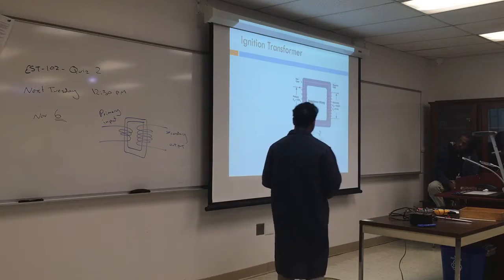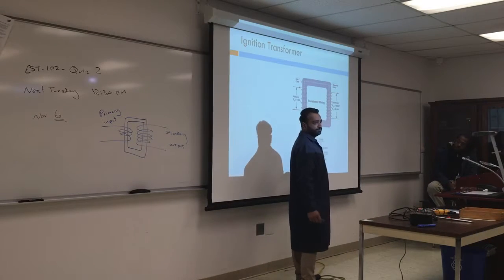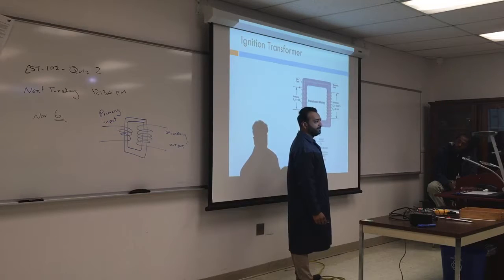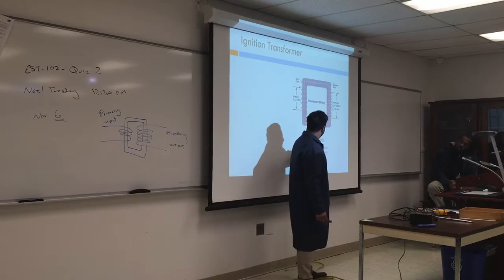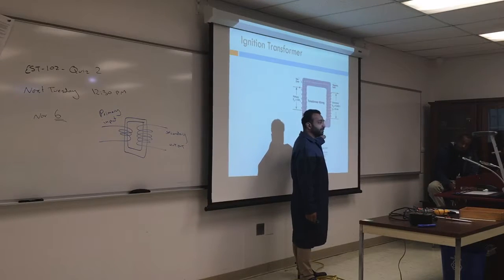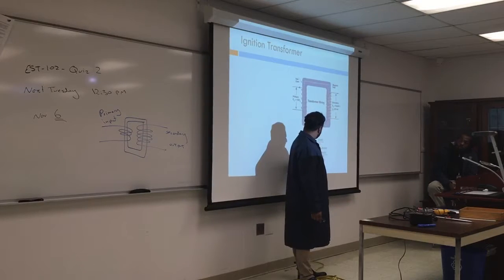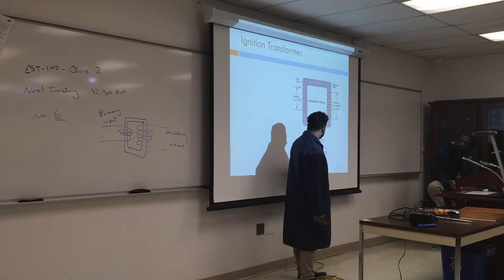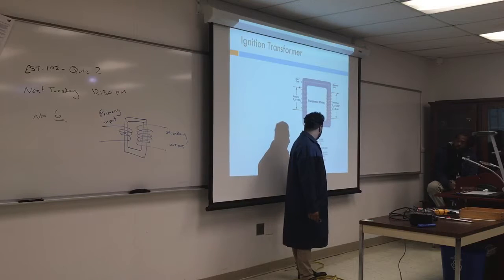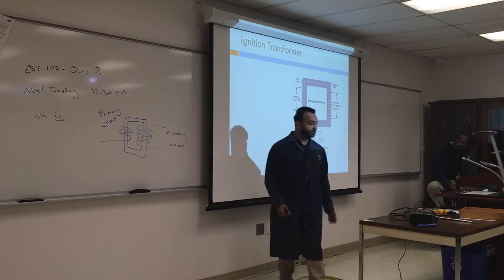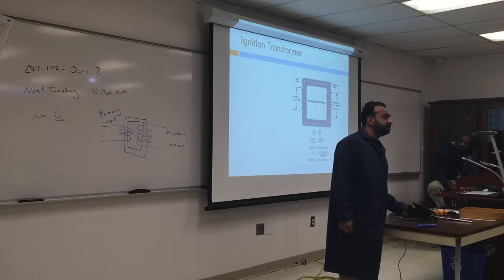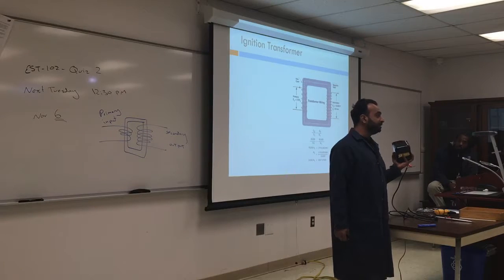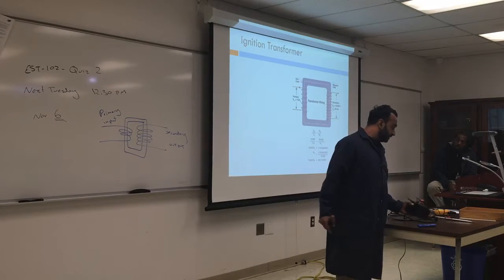This is an equation to tell you how many turns to go. You don't have to remember it, but it is very proportional. So this is voltage 2 over voltage 1 equals the number of turns at 2 over the number of turns at 1. Doing this equation, if I want to get 10,000 volts, I'm going to have to go 690 turns. That's why this transformer is huge. It has 690 turns of copper inside.